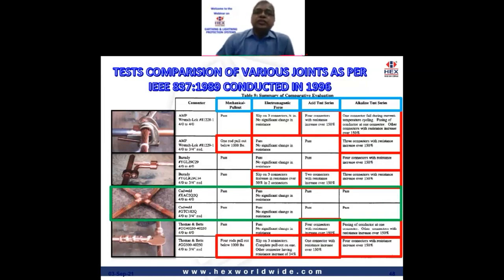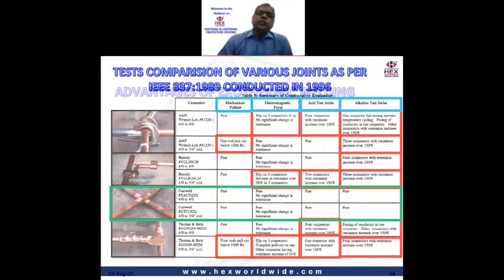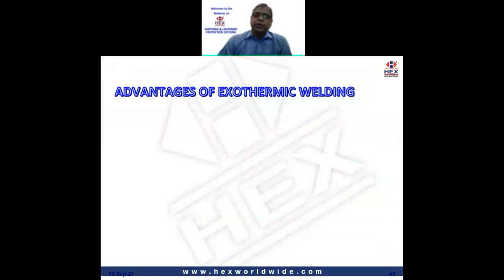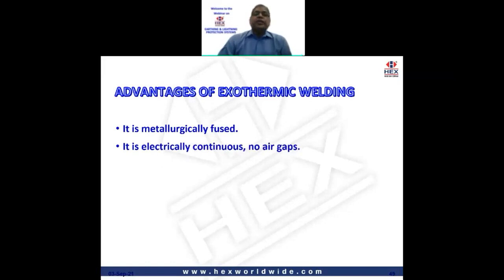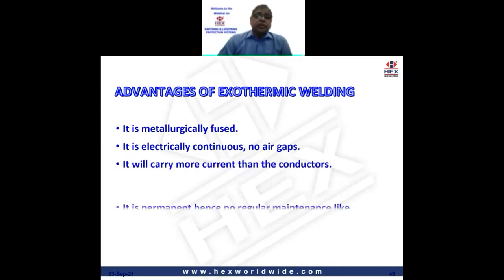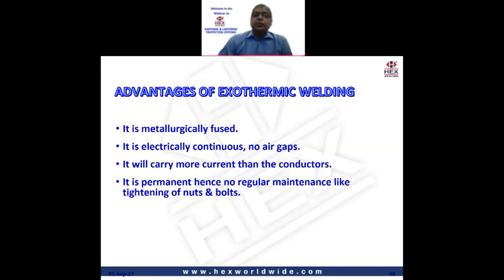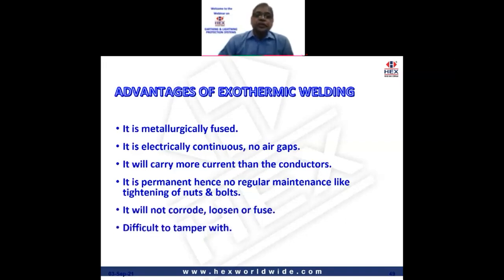Now, based on these results, it is concluded that exothermic welded connections are superior to mechanical and compression connections. So what are the advantages of exothermic welding? I'm sure you are already using this in the railways. It is metallurgically fused. It is electrically continuous. There are no air gaps like shown in that image previously. It can carry more current than the conductors at times. It is permanent, hence no regular maintenance like tightening of bolts and nuts. It will not corrode, loosen or fuse, and it is very difficult to tamper with.